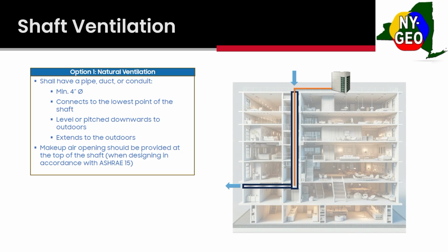So we've got a couple options for shaft ventilation. We've got mechanical and natural ventilation. Here we're showing the natural ventilation shaft. So the shaft pipe should be duct or conduit, minimum 4 inches. At the lowest point here, it needs to be pitched downwards outside. So again, refrigerant heavier than the air is going to sink to the bottom of the shaft and go out. And there should be a makeup air opening at the top to promote good draft going down the shaft there. So that's pretty simple. And you can run other utilities through your shaft. So if you've got any electrical, waste, whatever, you can run it all through the same shaft. It does not have to be just your refrigerant lines.